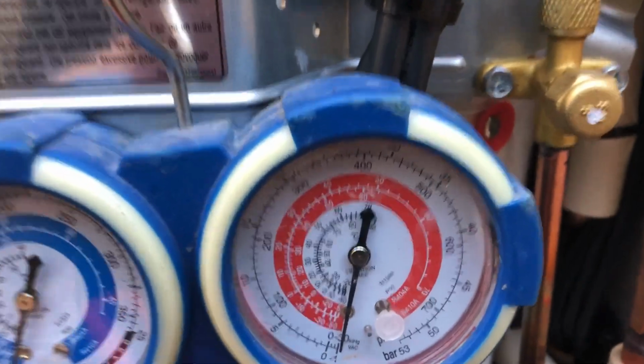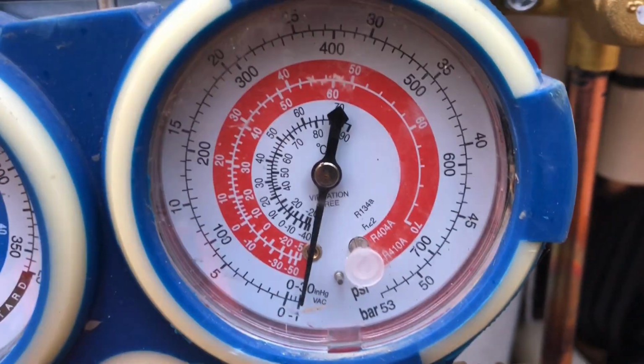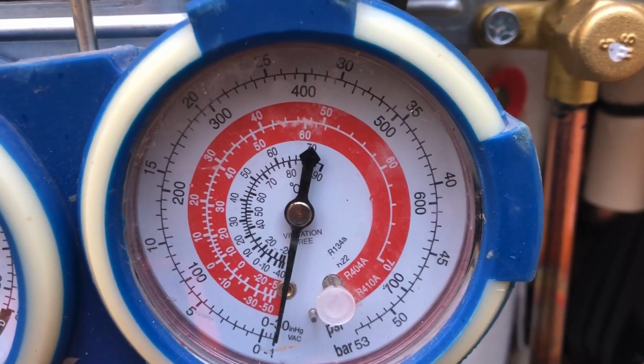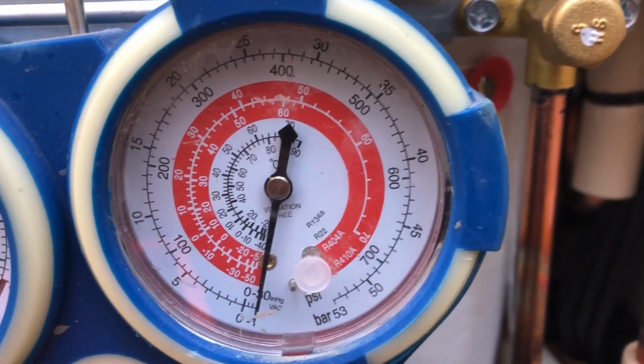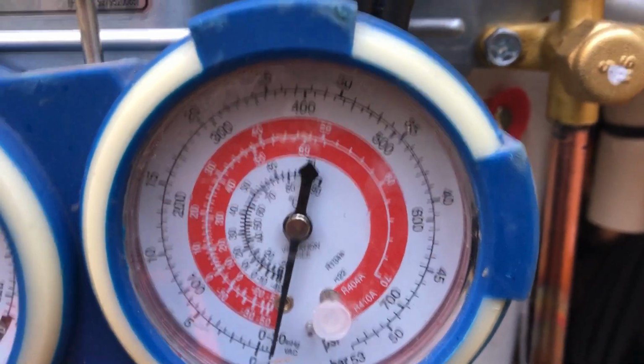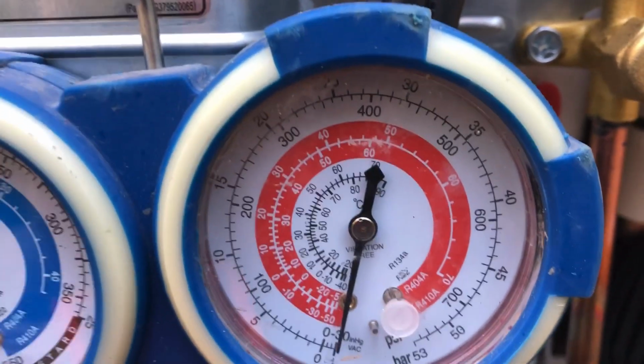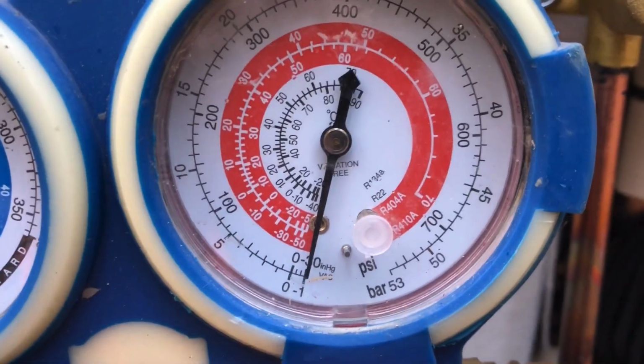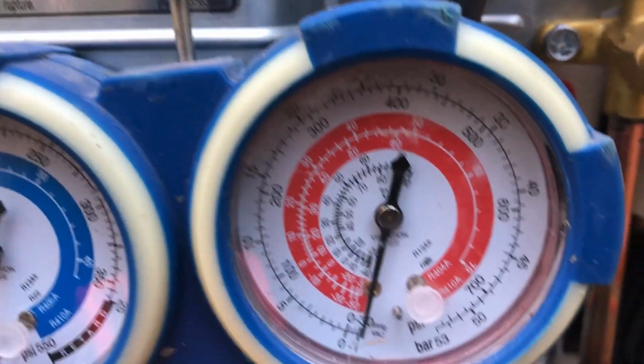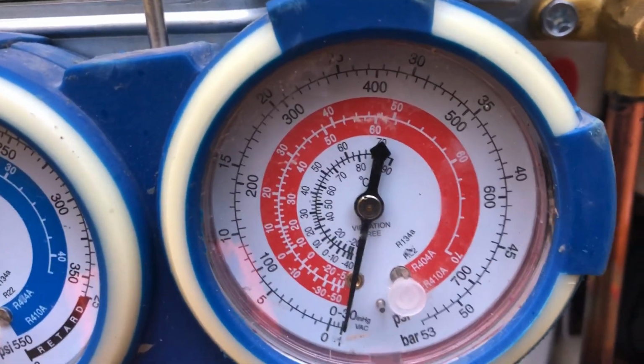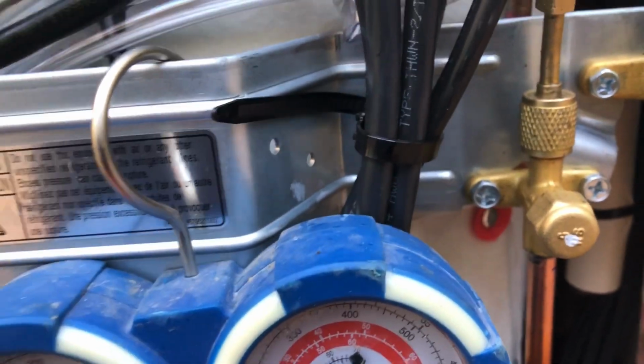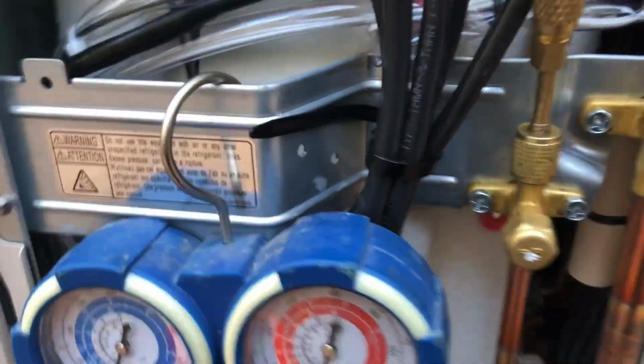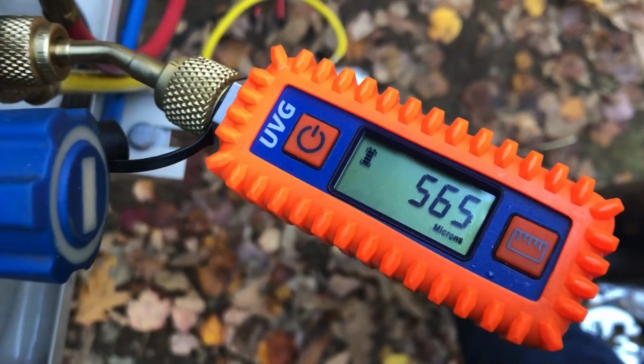What I'm looking for is making sure that this has dropped to -30. Now this gauge is a homeowner gauge, so it's not calibrated. I would have to calibrate it, but I don't really care. I know that it dropped just to -30. If you look at this one, it's not calibrated, so it's higher, but you can calibrate it if you care. In my case, I just use the red side because I know that's fine. Now, it's dropped to -30. I know with this micron level, I don't have any leaks.